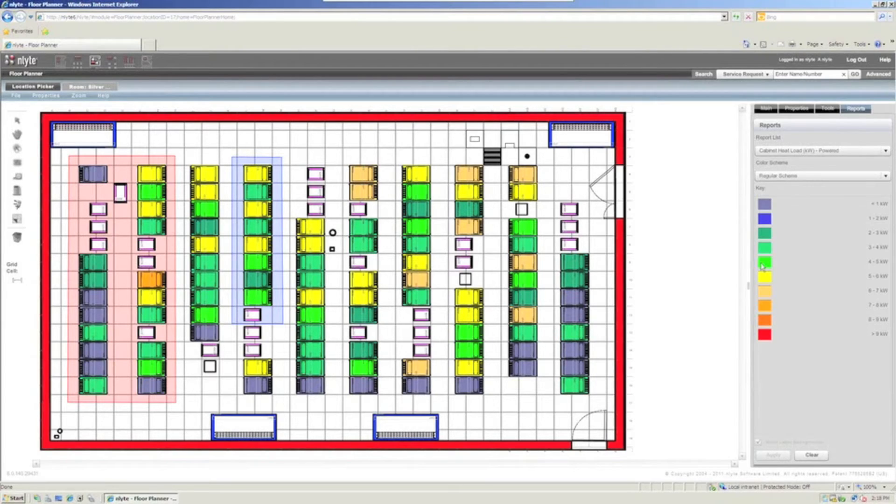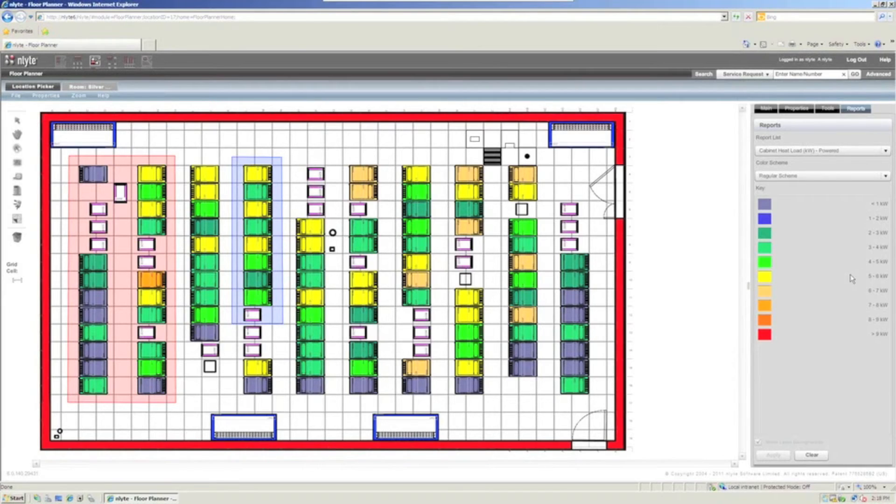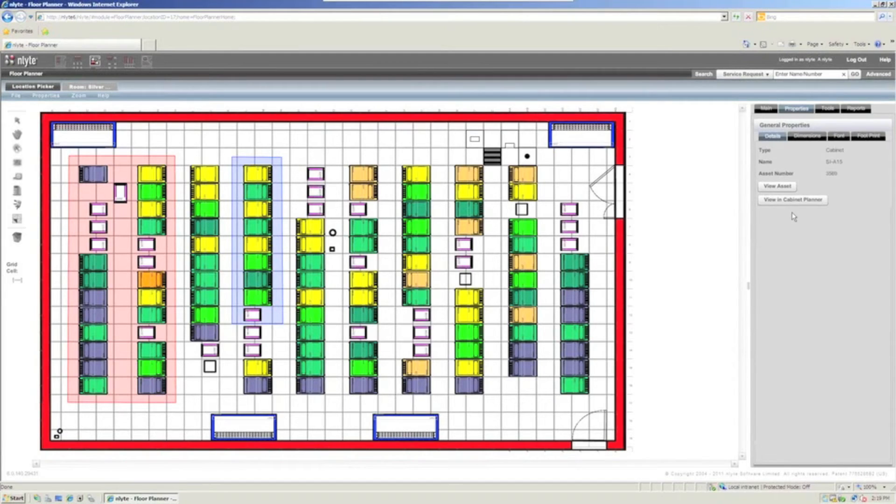So now as I look at all of these servers and the racks in here, I can see that I'm really not too bad. I tend to be down in the green and yellow range, which is below my threshold of how hot I want a cabinet to be, with the exception of this one here is kind of getting up into that seven or eight kilowatt range. So I would probably, again, as the manager of the data center here, maybe want to take a look at that particular cabinet. So I can just double click on it and say I would like to view that asset.